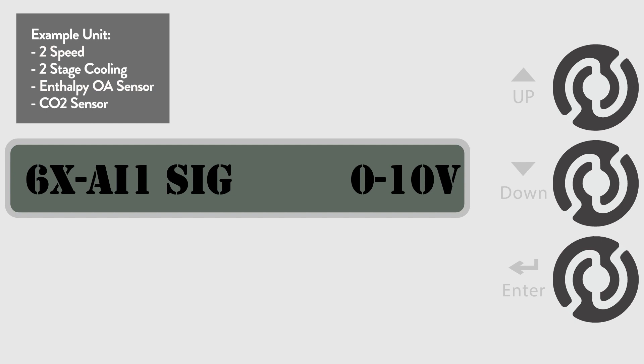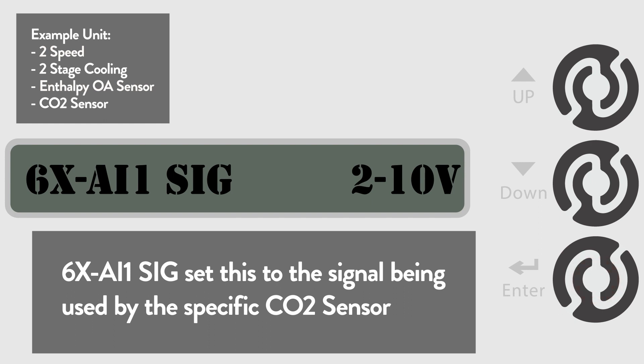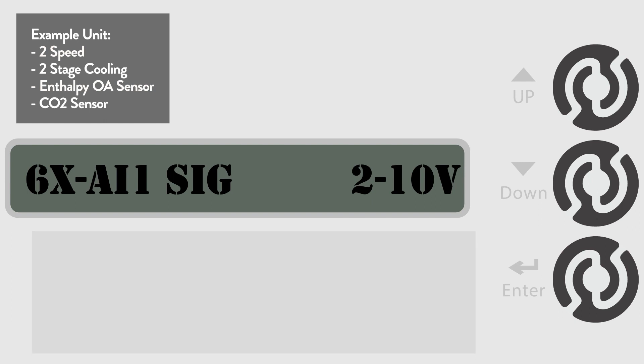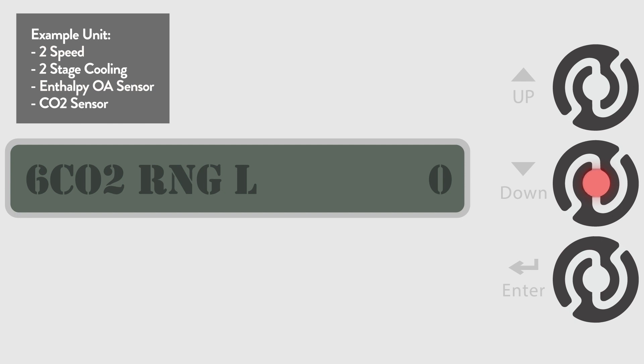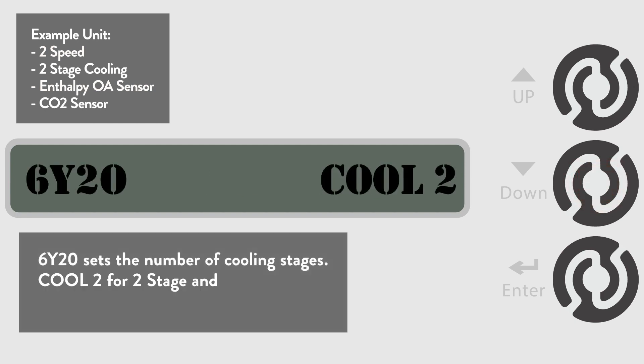Now scroll to the 6X-AI1 SIG menu to set what type of signal is sent to the CO2 sensor. The default is 0 to 10 volts, but for this example we are going to change it to 2 to 10 volts. Now let's go to 6Y20. This sets the number of cooling compressors. The default is COOL2 for two compressors. If your unit only has one compressor, change this setting to none.